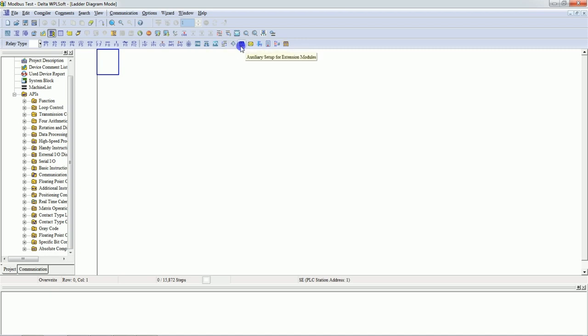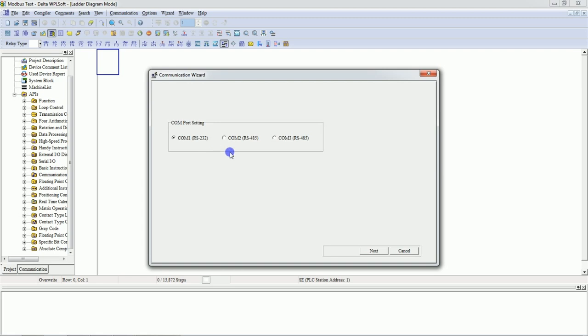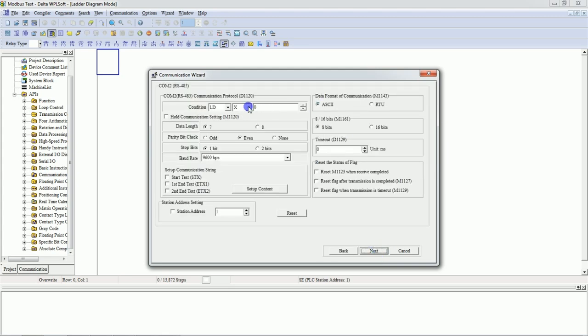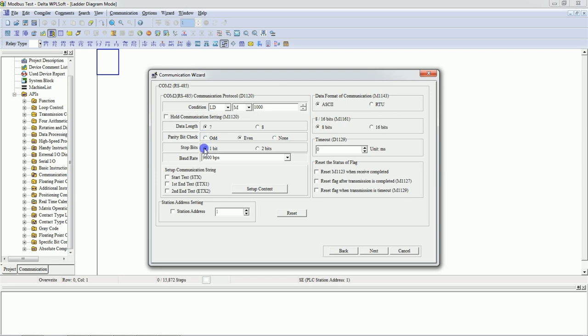You can see here the communication setup. This is the communication program — just click on this. We are going to use COM2 RS485 — select RS485, click Next. We will add M1000, which means always-on bit. These are the communication protocols. Click on 'Hold Communication Setting'. These are the parameters of RS485: seven data bits, even parity, one stop bit, baud rate 9600. We are going to use ASCII mode.